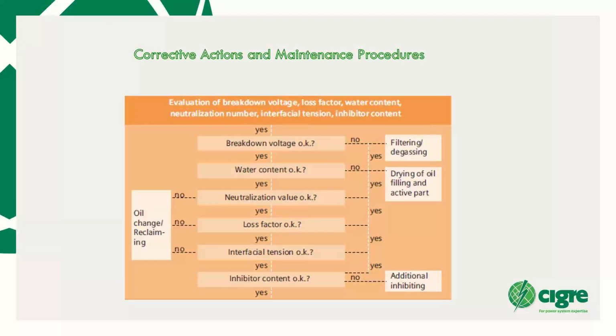Okay, if we have a transformer which is wet, what can be done in order to prevent breakdown and a fault? Of course, there are different kinds of schemes which can be used, depending on what can be done when the breakdown voltage is low, whether the water content is high, and so on. It makes less sense to dry only once by degassing the liquid, because usually insulating oils do not dissolve so much water that a transformer can be dried by it, except in a continuous mode.